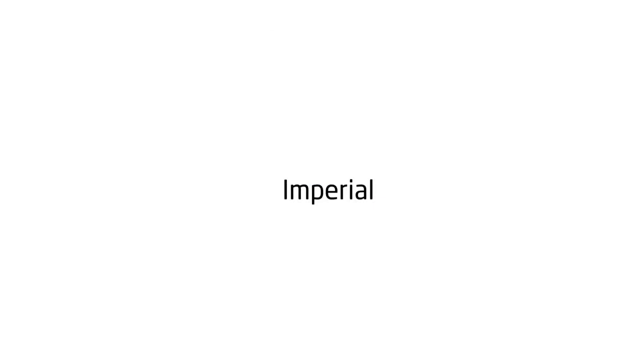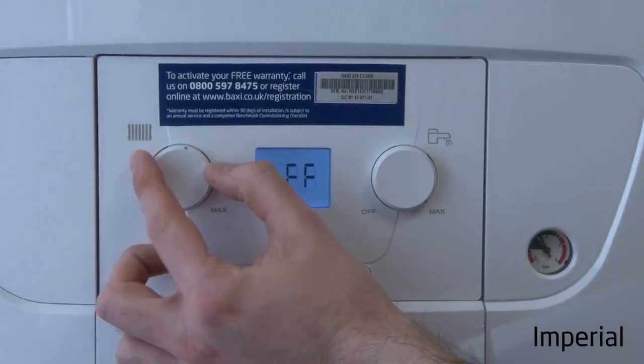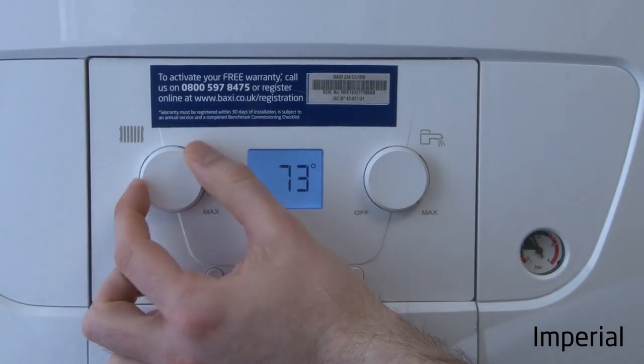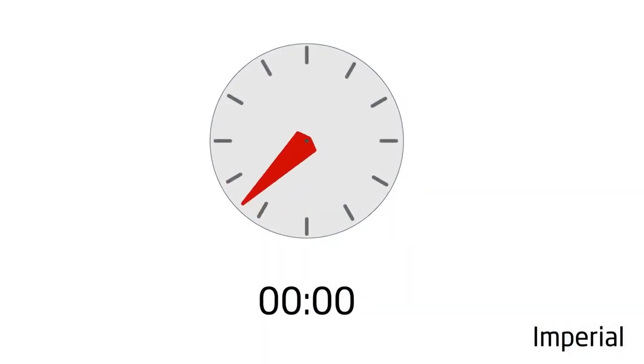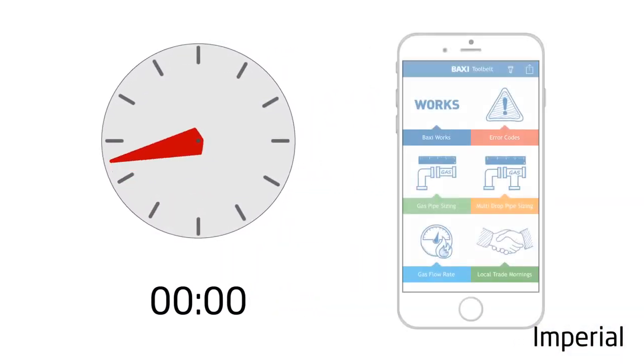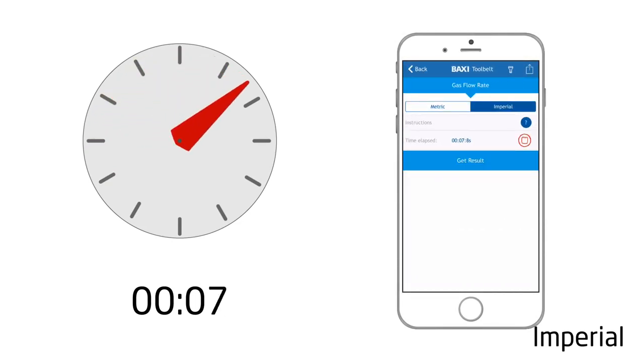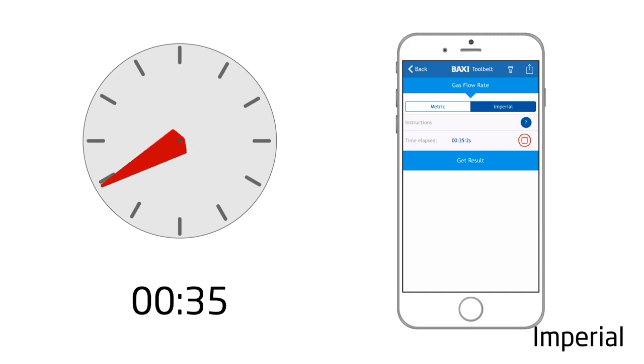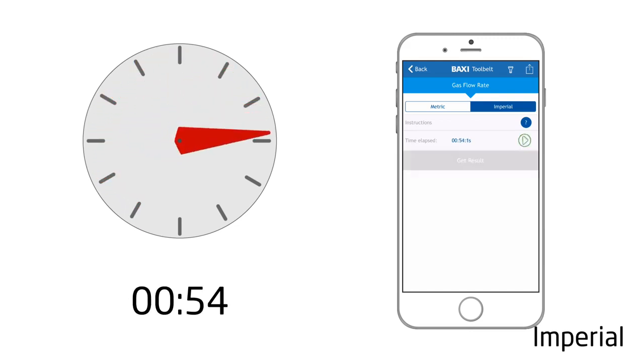If your gas meter is reading in Imperial then you should do as follows. Start the boiler on maximum workload, wait until the needle of the meter is in the 12 o'clock position and start the timer. Once the needle has completed the full rotation and returned to its start point, stop the timer and press get results.